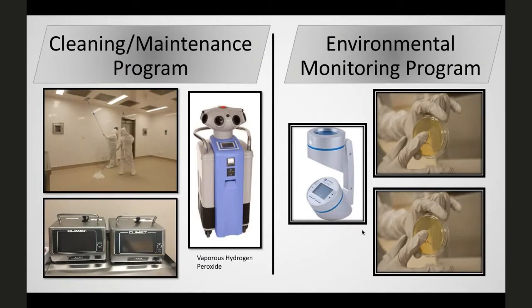So we shut off our air handlers and tape all the doors shut, and then we put the robot in the clean room, and it spews out vaporous hydrogen peroxide out of its head here and kills everything in the room. So we can even open up all of the incubator doors and fridges, and the vaporous hydrogen peroxide gets into all the nooks and crannies that can be difficult to clean manually.